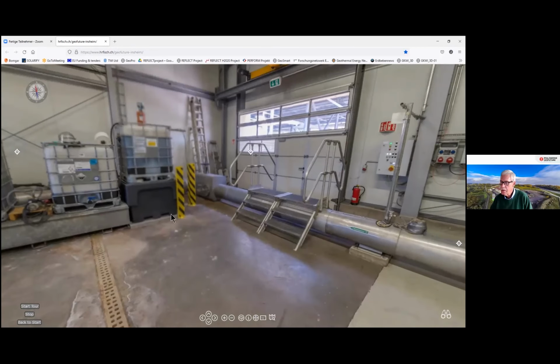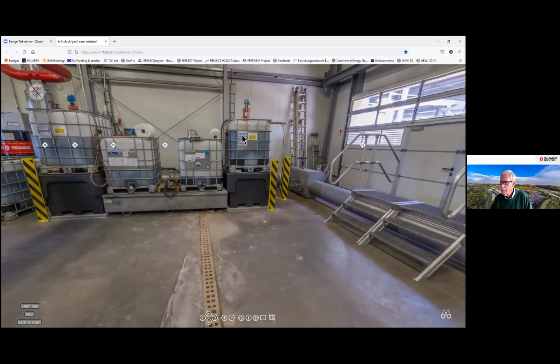After these filters, the brine passes by two inhibitor stations. One is an organic acid preventing barium sulfate from scaling out in our brine. This is very important, as the radioactive isotope lead-210 precipitates in combination with barium sulfate. So when we reduce the amount of precipitating barium sulfate, we automatically reduce the NORM storing as well. The second inhibitor is a corrosion protection fluid, which sets up a corrosion protection film within our piping system and helps to reduce further precipitation effects.